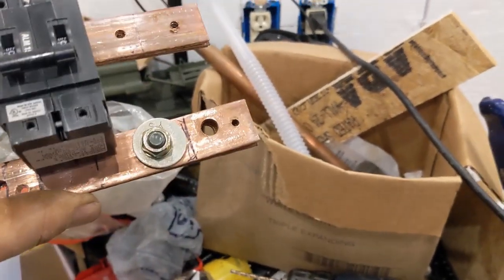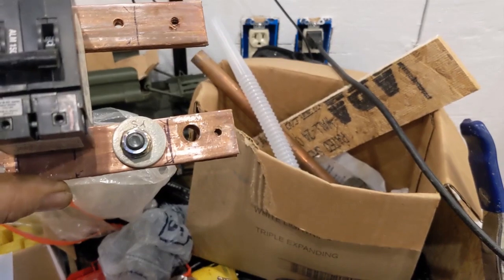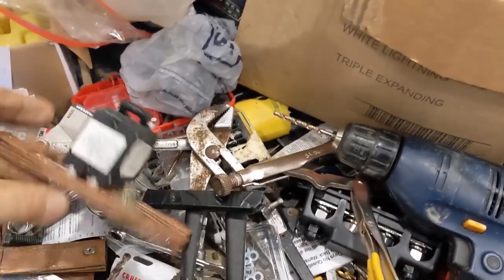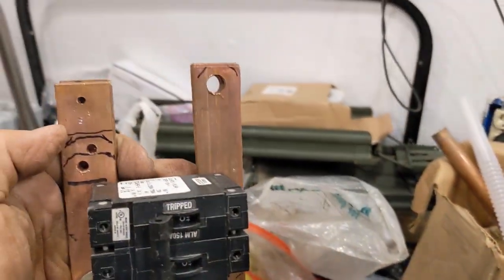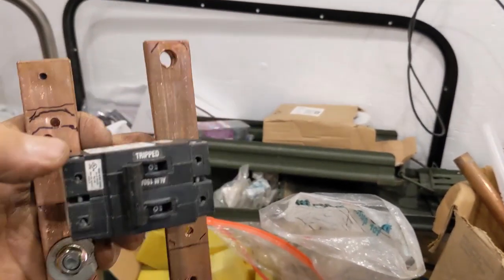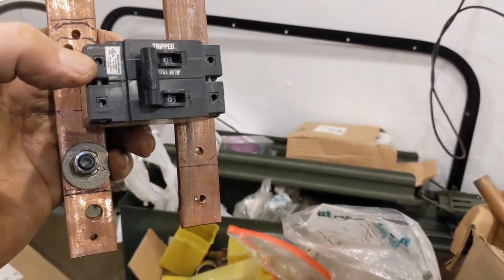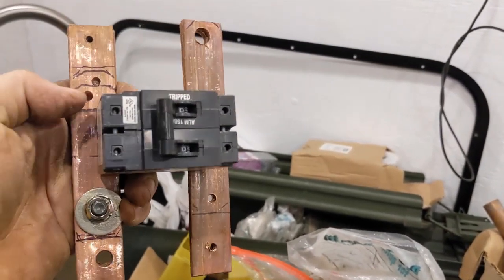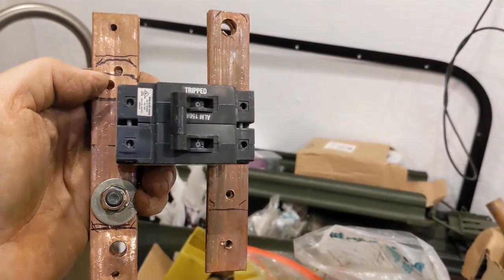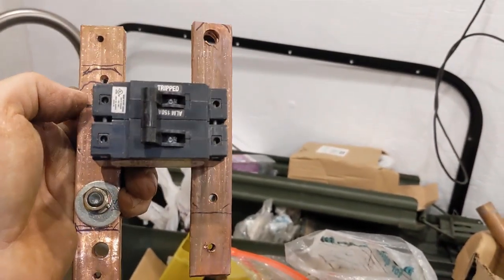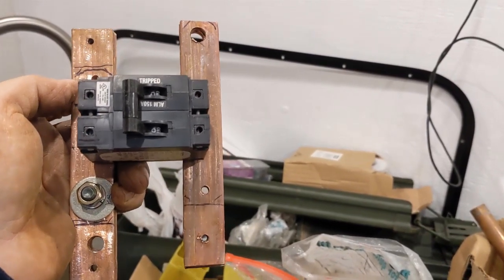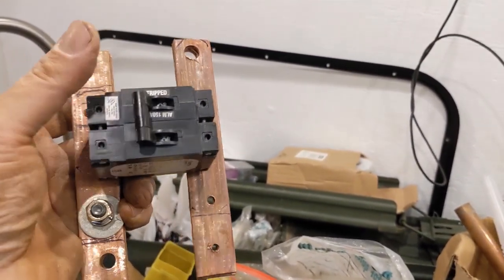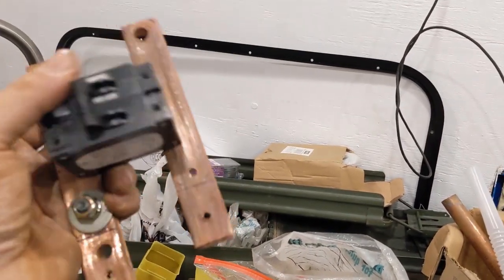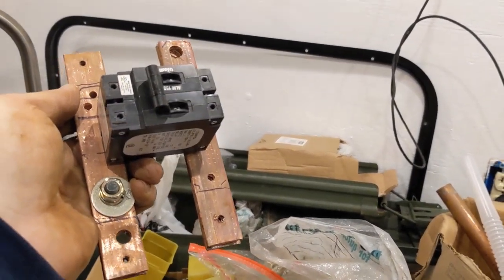Alright, so here this bus bar is in position. I've got that bolt there so I can put the positive inverter cable on. This will basically hang on the bus bar on the second terminal in, and go off to the side a bit, where the inverter cable will clamp on. The other holes are to mount this with some screws and standoffs, maybe made out of wood with holes drilled. I'm going to wrap these bus bars in red tape to help protect from people touching them.